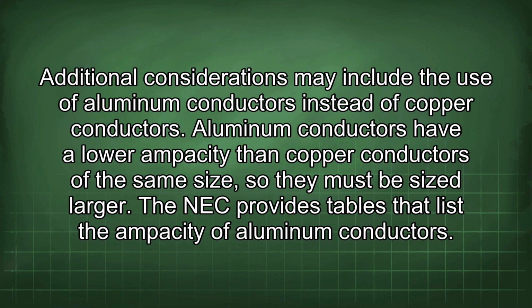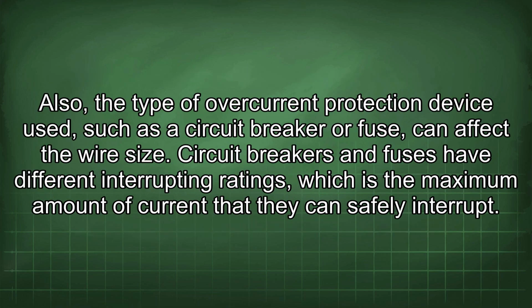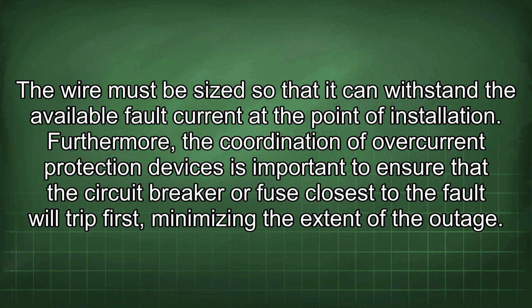The NEC provides tables that list the ampacity of aluminum conductors. Also, the type of overcurrent protection device used, such as a circuit breaker or fuse, can affect the wire size. Circuit breakers and fuses have different interrupting ratings, which is the maximum amount of current that they can safely interrupt. The wire must be sized so that it can withstand the available fault current at the point of installation.